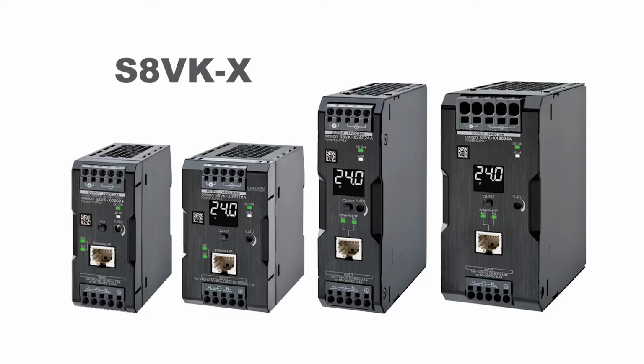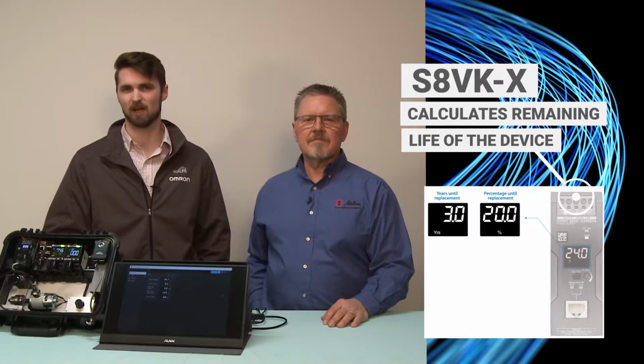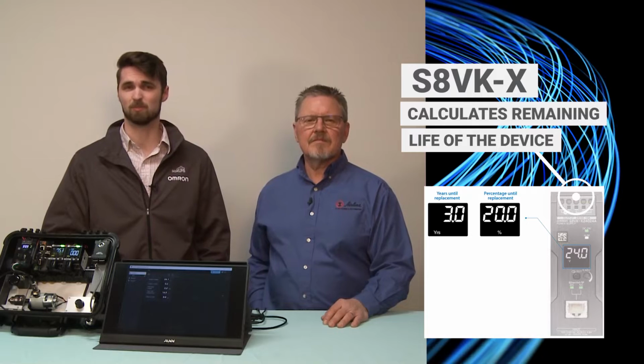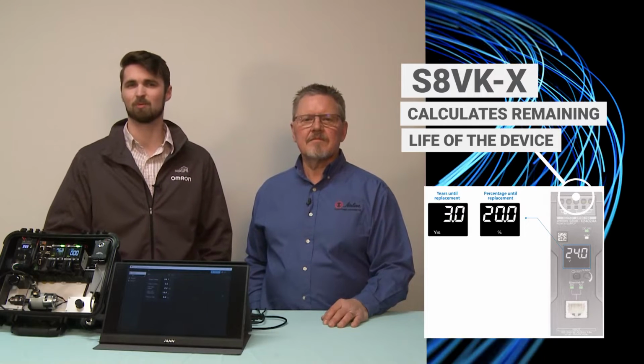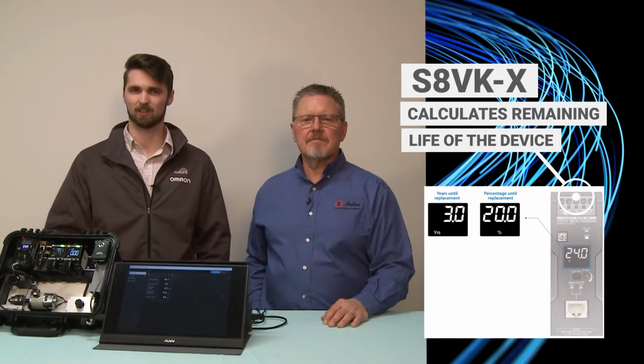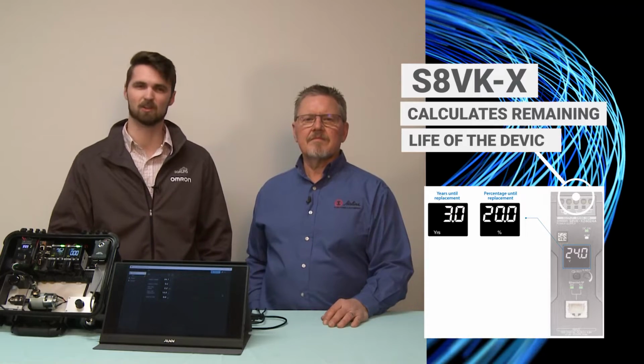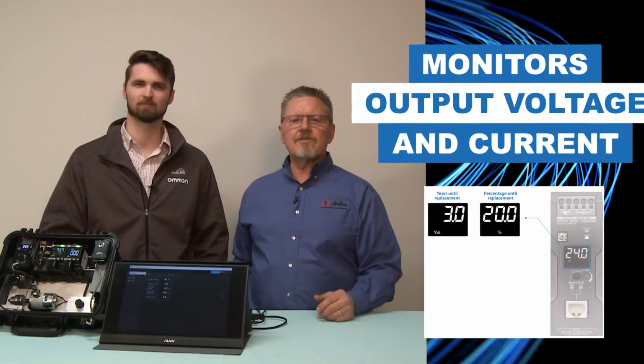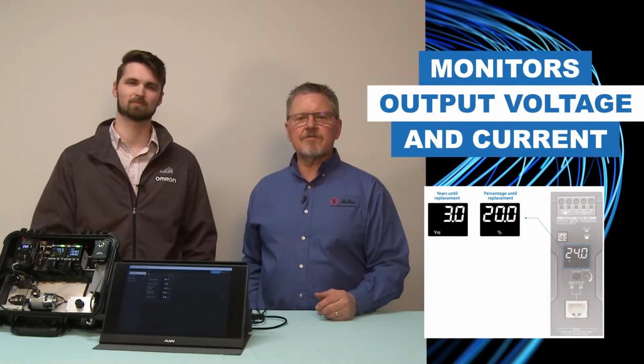The S8VK-X is one of our most advanced power supplies that we offer. The first step in scheduled maintenance is knowing when to replace your power supply. The S8VK-X calculates the deterioration of the internal electrolytic capacitor based on its component's temperature. This way it knows exactly how many years it has left and exactly the remaining lifetime percentage of the device. And that's all viewable via the on-unit display. It also monitors output voltage and current, critical metrics in optimizing the lifetime of any power supply.